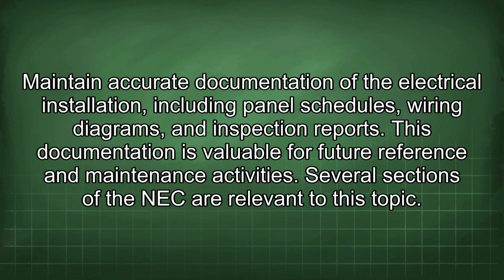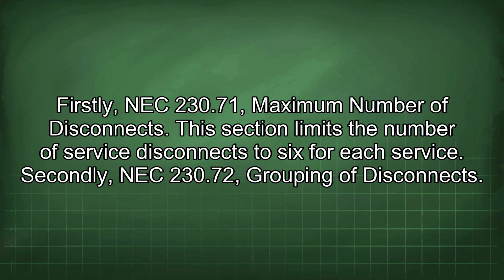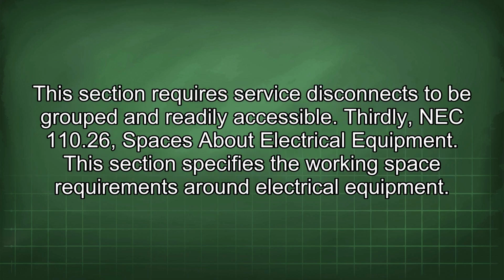Several sections of the NEC are relevant to this topic. Firstly, NEC 230.71, maximum number of disconnects. This section limits the number of service disconnects to 6 for each service. Secondly, NEC 230.72, grouping of disconnects. This section requires service disconnects to be grouped and readily accessible.